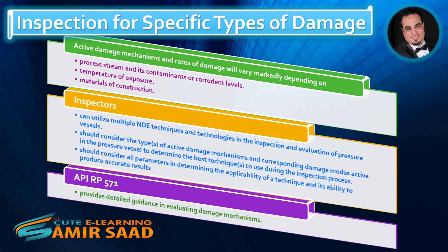Inspection for specific types of damage: active damage mechanisms and rates of damage will vary markedly depending on the process stream and its contaminants or corrodent levels, temperature of exposure, and materials of construction. Inspectors can utilize multiple NDE techniques and technologies in the inspection and evaluation of pressure vessels. Inspectors should consider the types of active damage mechanisms and corresponding damage modes active in the pressure vessel to determine the best techniques to use. The inspector should consider all parameters in determining the applicability of a technique and its ability to produce accurate results.